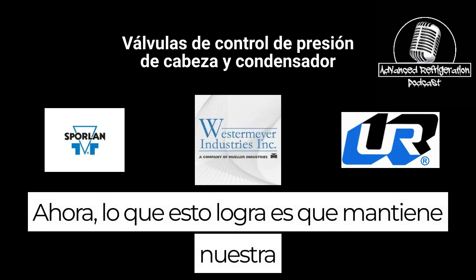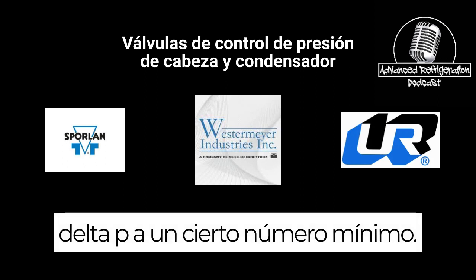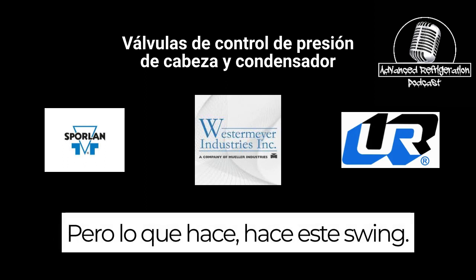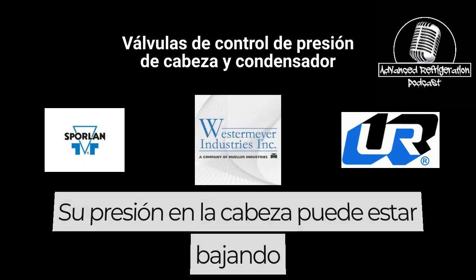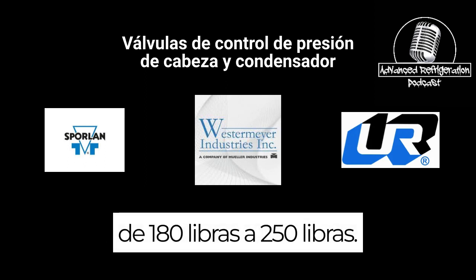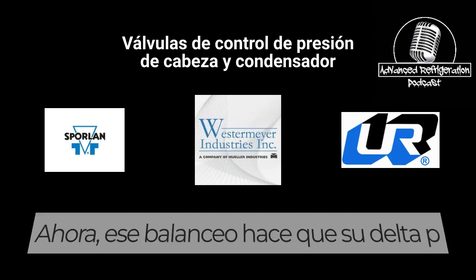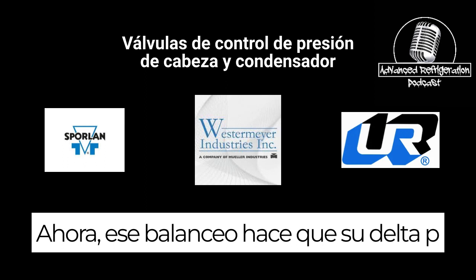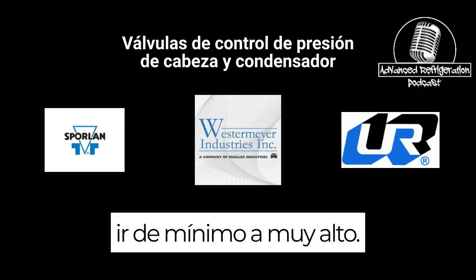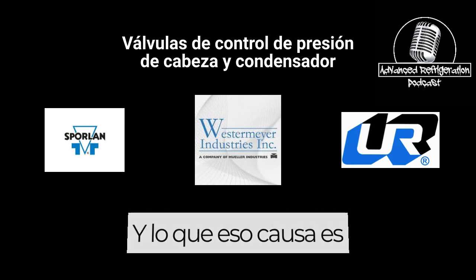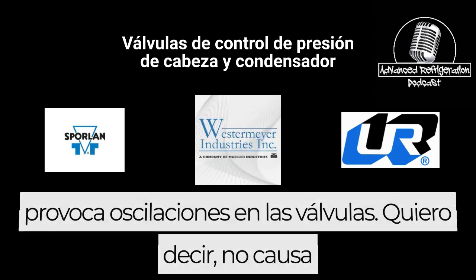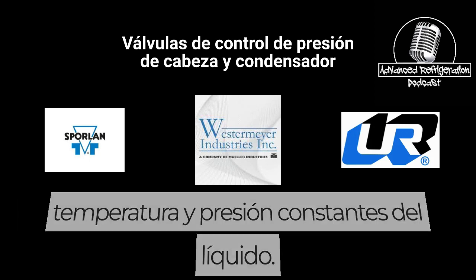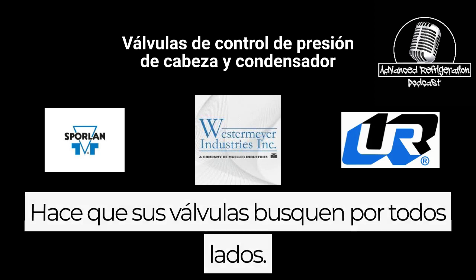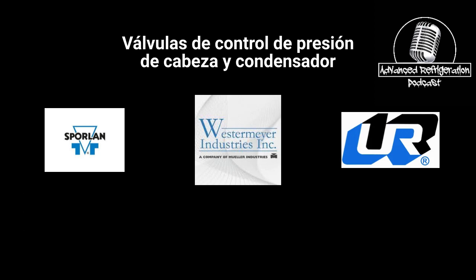Now, what this accomplishes is it keeps our delta P to a certain minimum, but it makes this swing. Your head pressure may be going from 180 pounds to 250 pounds. And this is an example. Now, that swinging causes your delta P to go from bare minimum to really high. And what that causes is hunting in the valves. I mean, it doesn't give steady liquid temperature and pressure. It causes your valves to hunt all over the place.